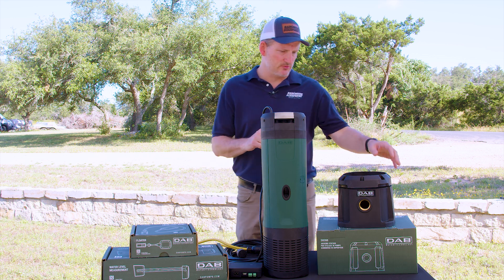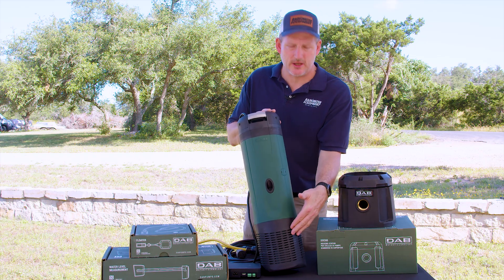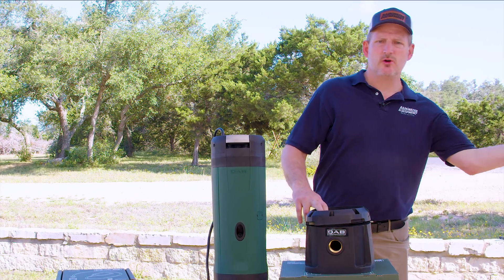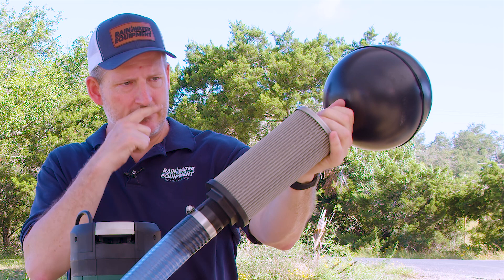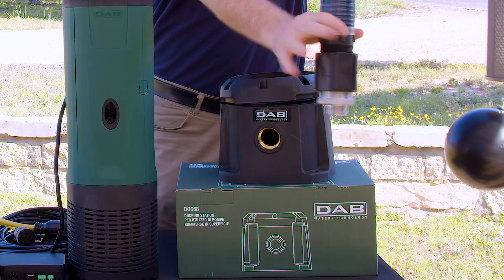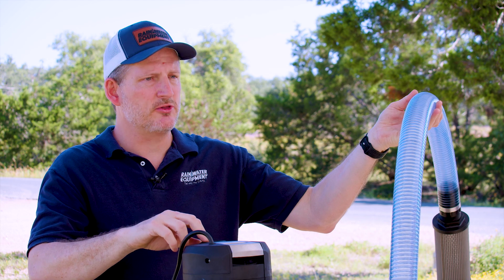The E.sybox Diver comes with an optional accessory called the Dock 68. What the Dock 68 allows you to do is remove the base on the pump that has a filtered screen and replace it by setting the pump into this dock, and then you can connect a floating filter to the Dock 68. In rainwater applications, you often want to pull water from just below the surface in your water storage tank. We have a 2-inch floating filter with a stainless steel mesh screen that filters water to 250 micron, and the adapter on the end of the hose will screw right into this base. When the pump turns on, it will pull water through this hose and then discharge it out of the top of the pump through this inch and a quarter female-threaded discharge.